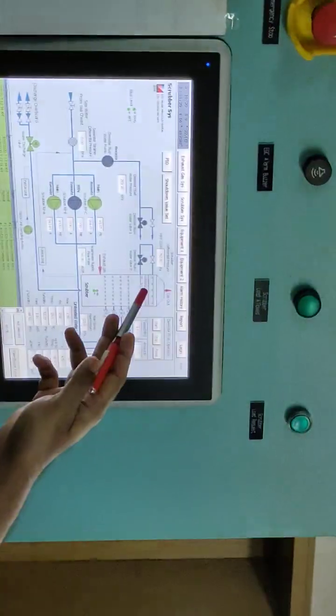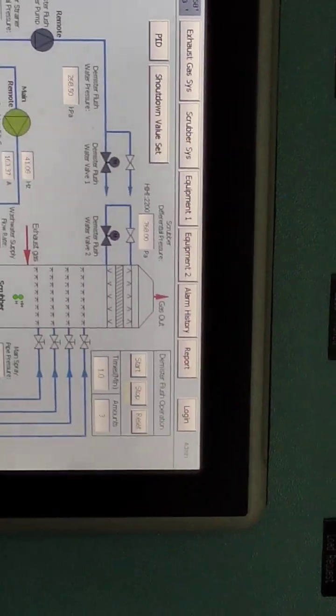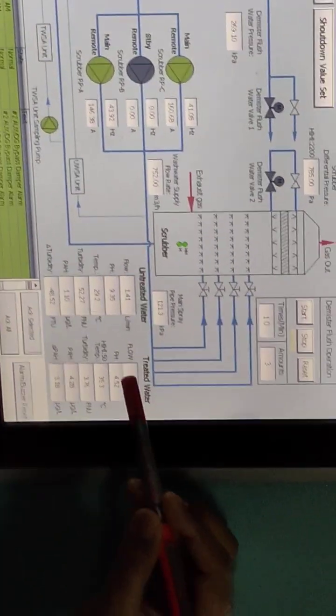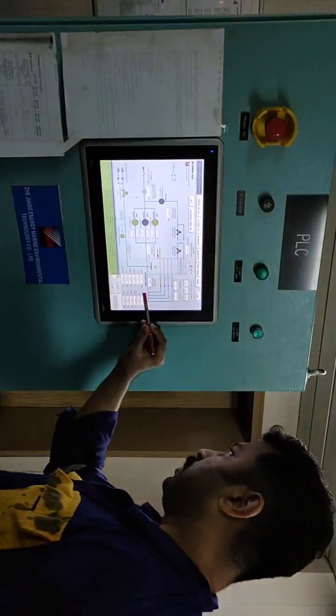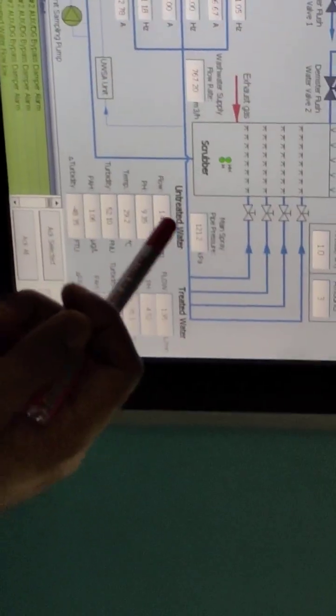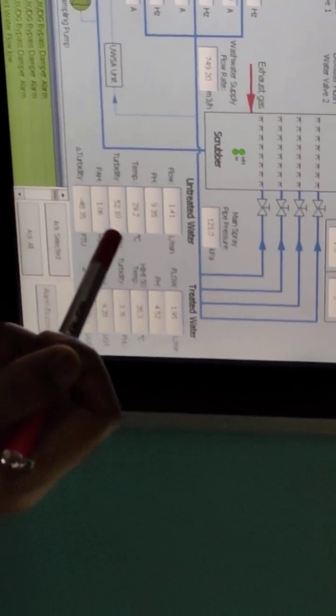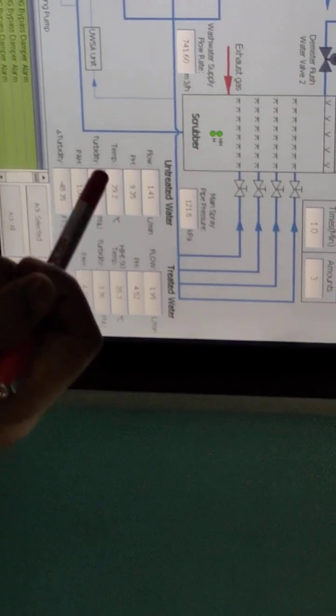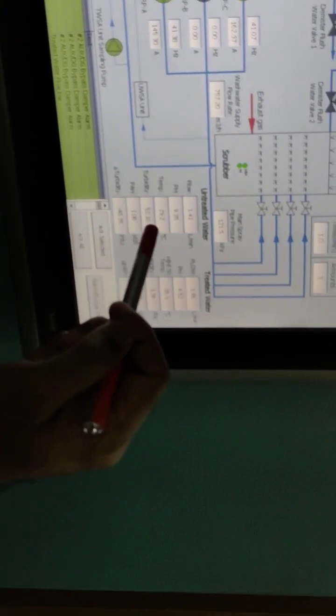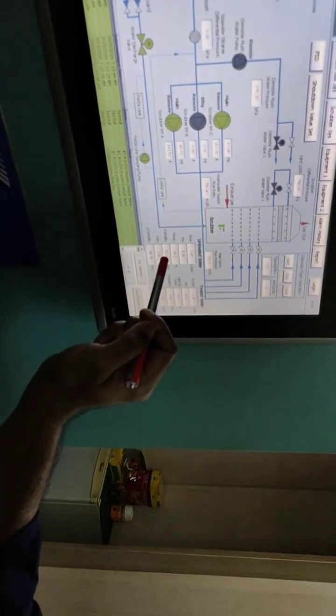This is out, and this differential pressure, you know, is sensing how clean the demister is. And regarding these values, come a little close. So you see the flow in, out. Inlet pH how much, outlet pH how much, inlet temperature, outlet temperature, turbidity. This is where the issue is. You see the turbidity of the inlet is 52 and the outlet is 3. Actually it's supposed to be the other way. There is something wrong with the calibration of the untreated water turbidity sensor.